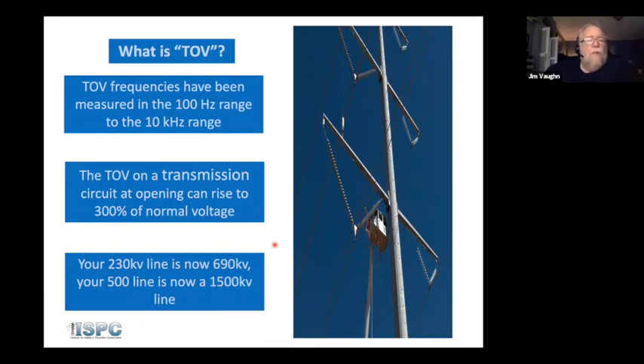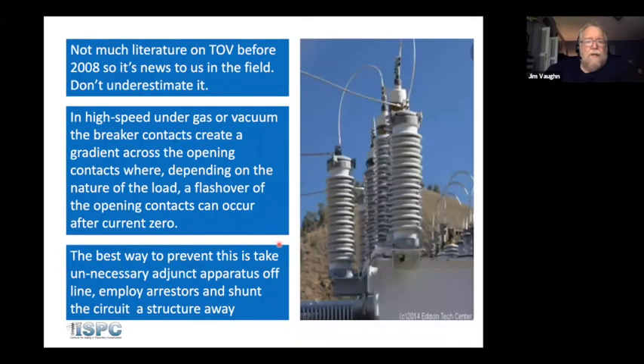Now, we work at 60 hertz. Our whole system, including our insulation system, is designed to withstand voltages at 60 hertz. When these TOVs occur, frequencies of voltage on the circuit can be up to the 10 kilohertz range, which can easily flash over an insulator that would not flash over at 60 hertz. A TOV on a transmission circuit can rise to 300% of normal voltage. And what that means is that the 230 circuit that you were working on is now 690, or the 500 circuit you were working on is now 1500 kV during this TOV event. So this is a serious thing that happens.